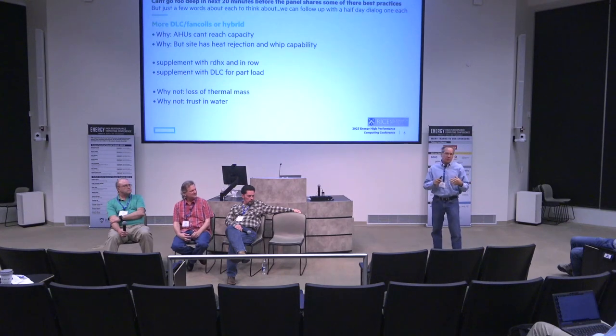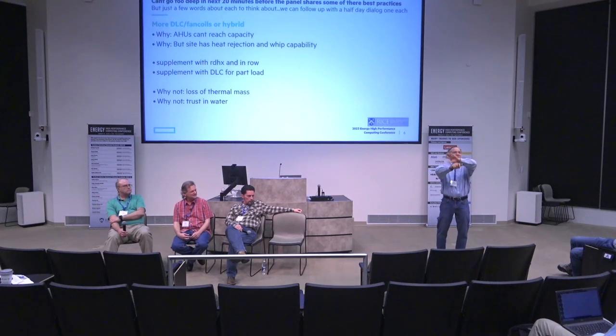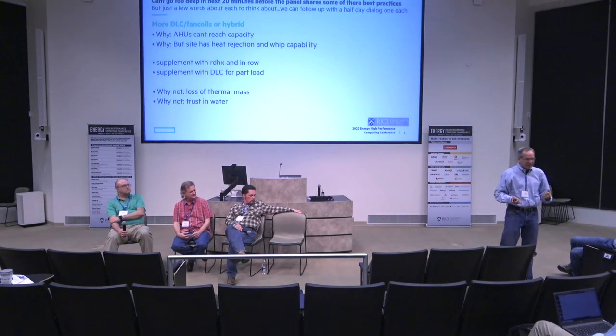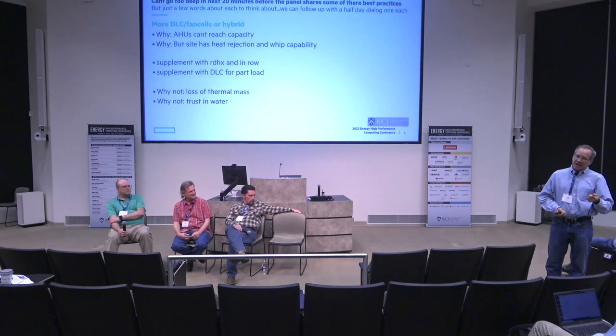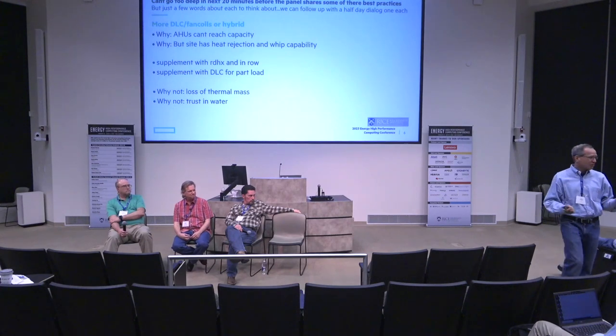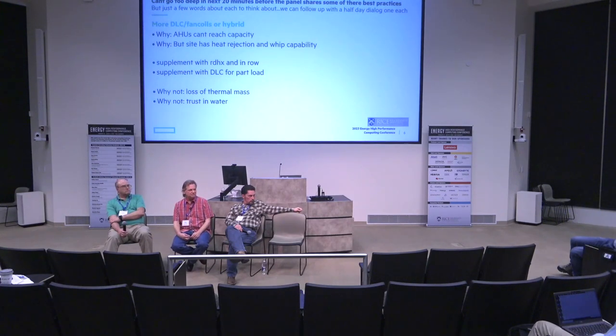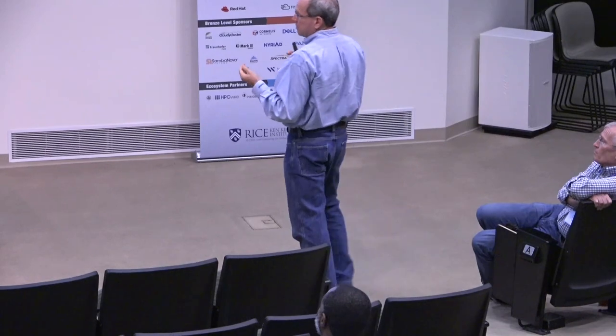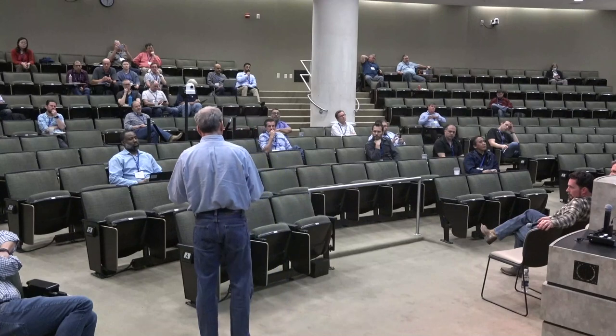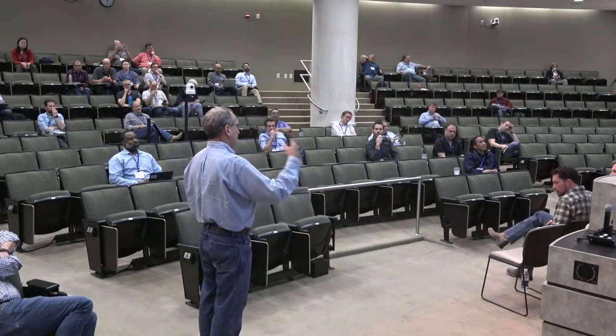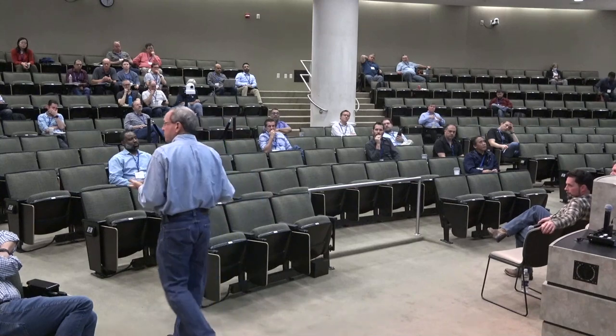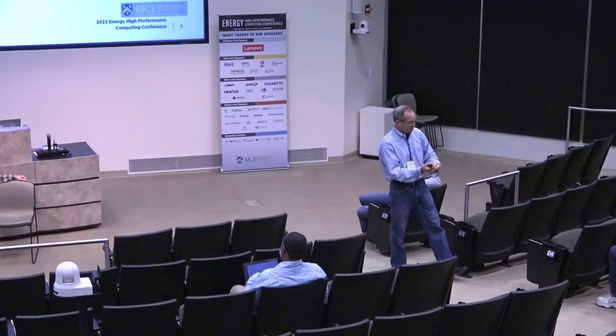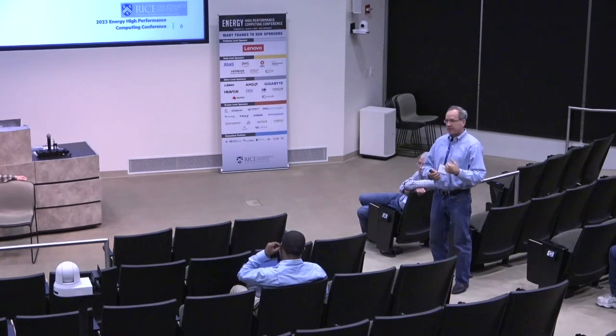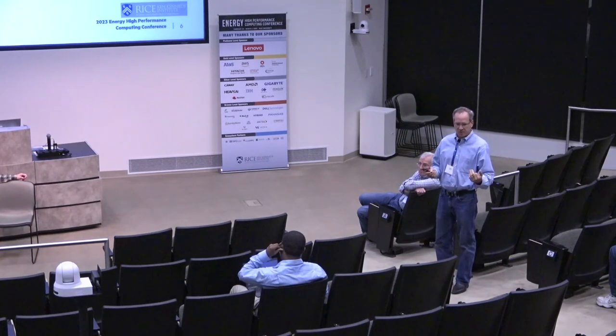What we've been finding, taking a survey of lots of deployments and decisions people are making, is they're actually not at their limits on the cooling tower. Cooling towers are kind of over-designed from a Delta T perspective. So they said, hey, what can I do by actually bringing the water instead to a computer room air handler? I can get 25% more capacity out of that water by bringing it into the room. But that's math you have to go do. You have to make sure your plant can deal with that, can deal with the pressure drop, because you don't want to break the air conditioner in the room.